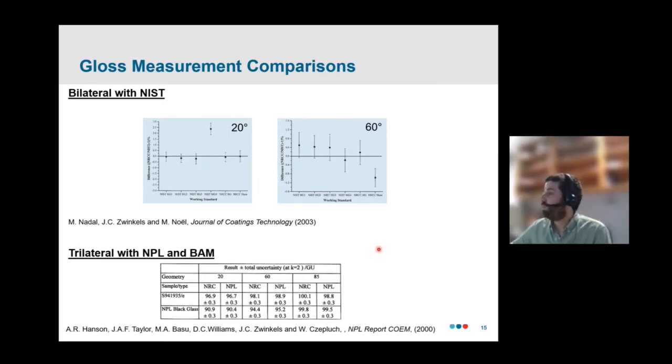Now, over the years, there have been a number of efforts in order to validate the performance of this instrument. One that I'll talk about a bit was done in 2003. This was a bilateral intercomparison done with NIST. And in this comparison, the two labs exchanged six samples and they were measured in both labs and the results compared. These are some of the results from that intercomparison. What's being shown in these plots is the relative difference in the scales at 20 and 60 degrees for the six different standards used in the study. And you can see that, for the most part, the two instruments or the two labs are in agreement within the stated uncertainties.